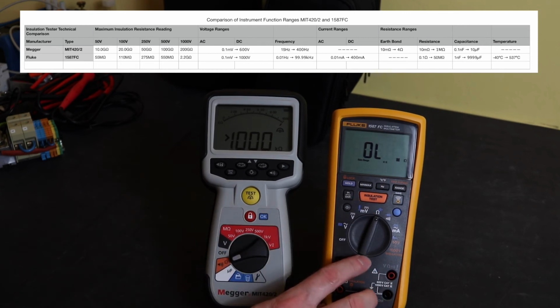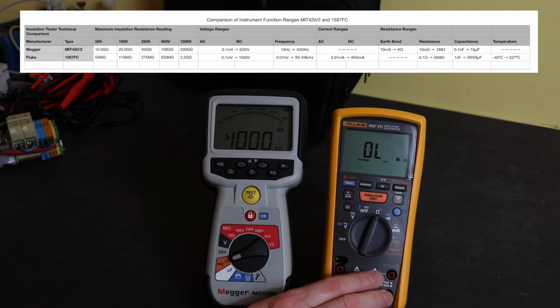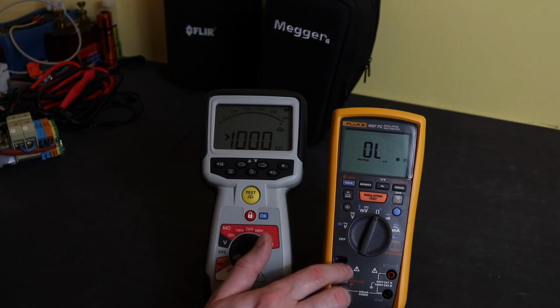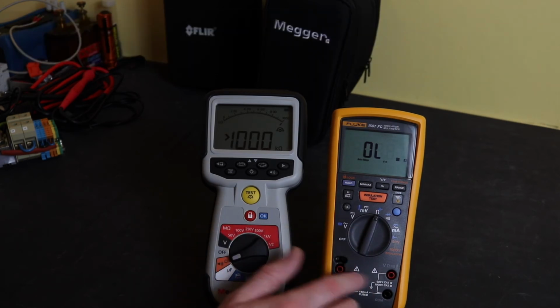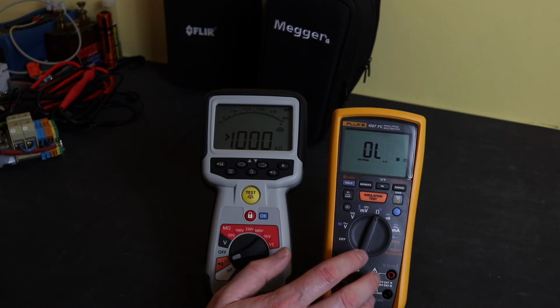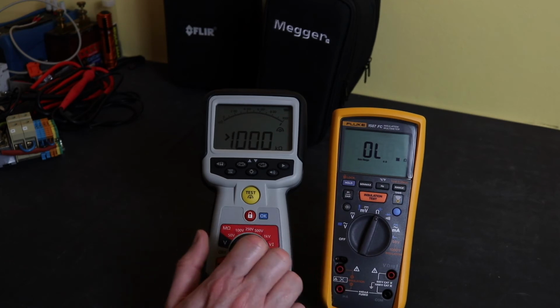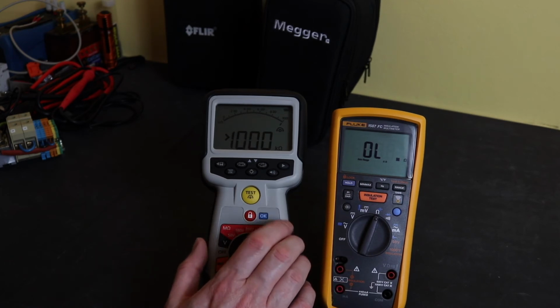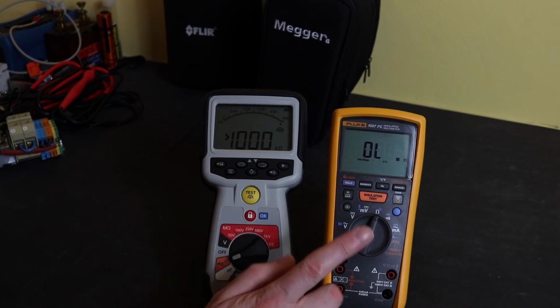For the Fluke over here, for the ohms scale, this will read 0.1 ohm up to 50 megohms. So again, kind of a multimeter style function, much wider reading capability than the Megger has. However, this doesn't have a 200 milliamp test current. It's a standard resistance range, 1 milliamp test current, something like that. So this instrument in that respect is not compatible with the continuity test function required under the UK wiring regs, which the Megger does meet with its 200 milliamp test current.